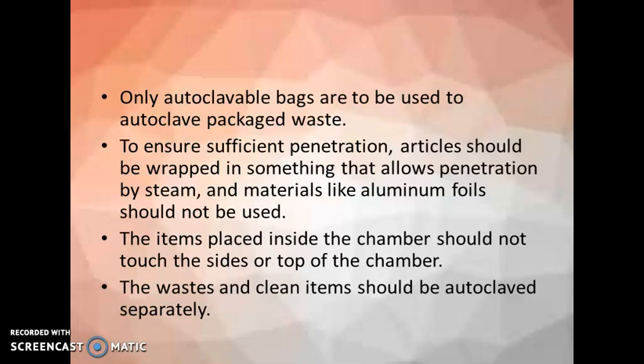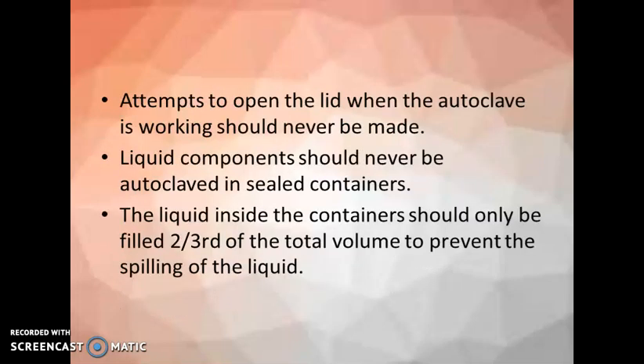The items placed inside the chamber should not touch the sides or the top of the chamber, and the wastes and the clean items should be autoclaved separately. So waste and clean items should be autoclaved separately, otherwise there is a chance of mixing together, causing massive contamination. Attempts to open the lid when the autoclave is working should never be made. Why? Because there will be a higher chance of explosion. So don't make those attempts.